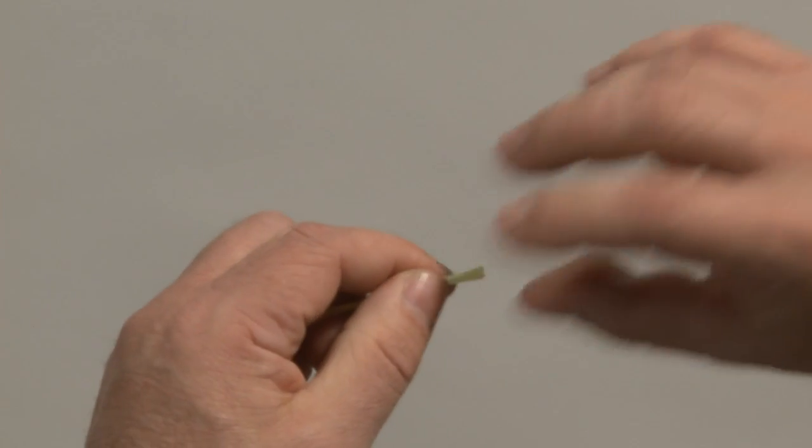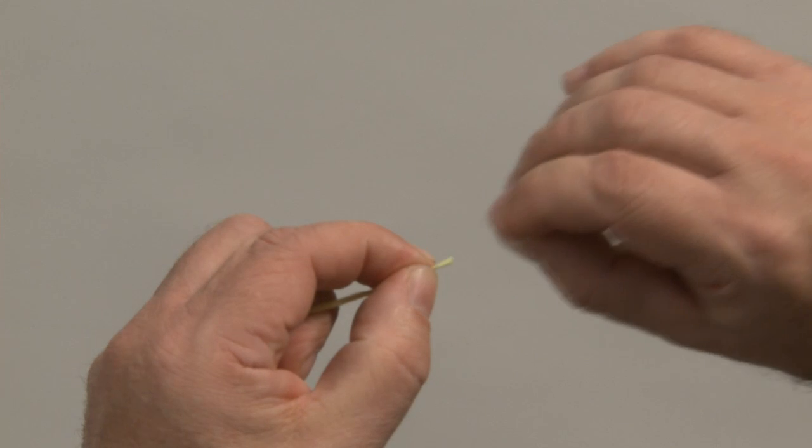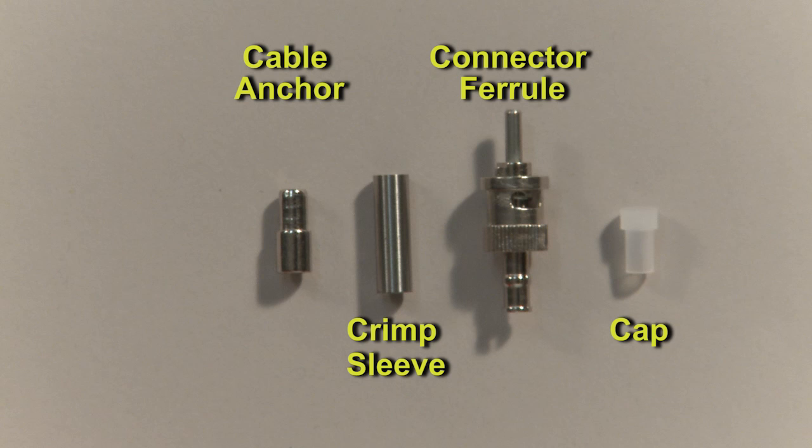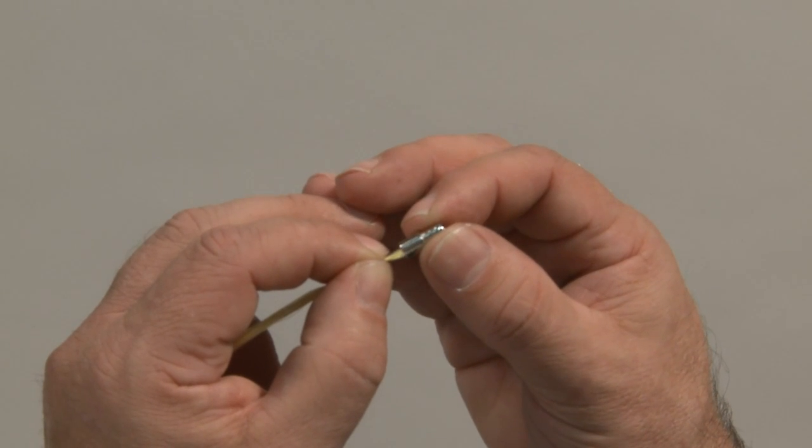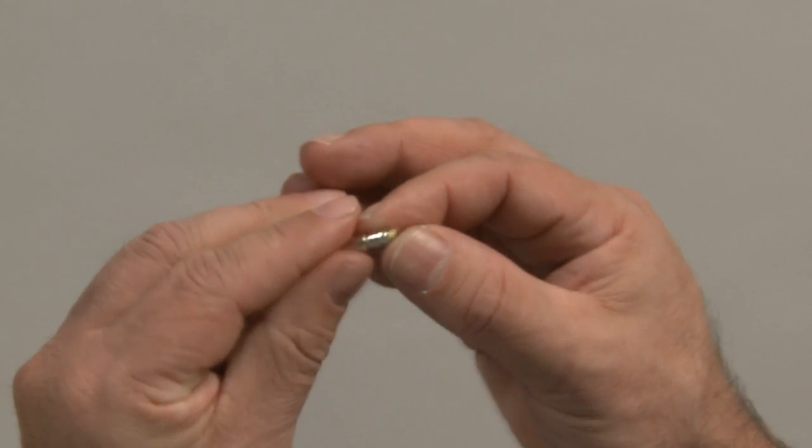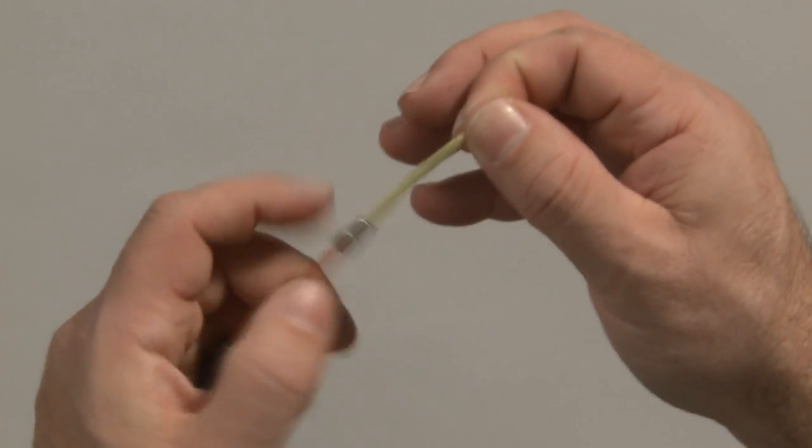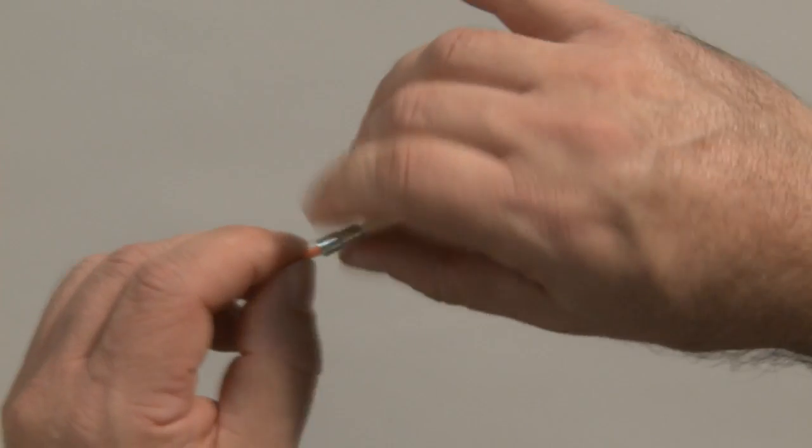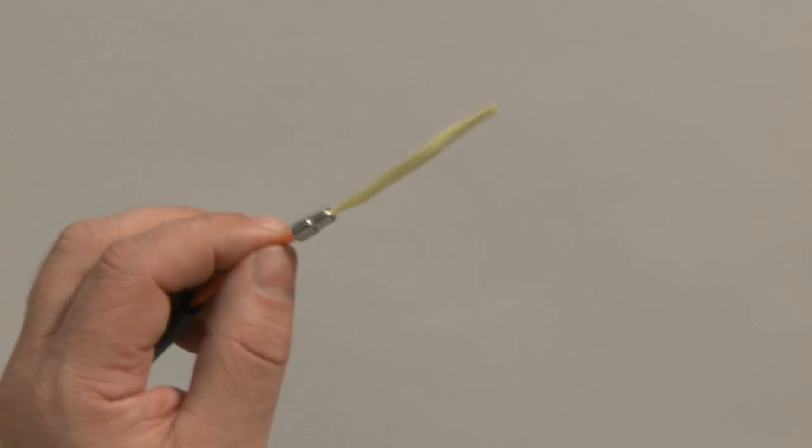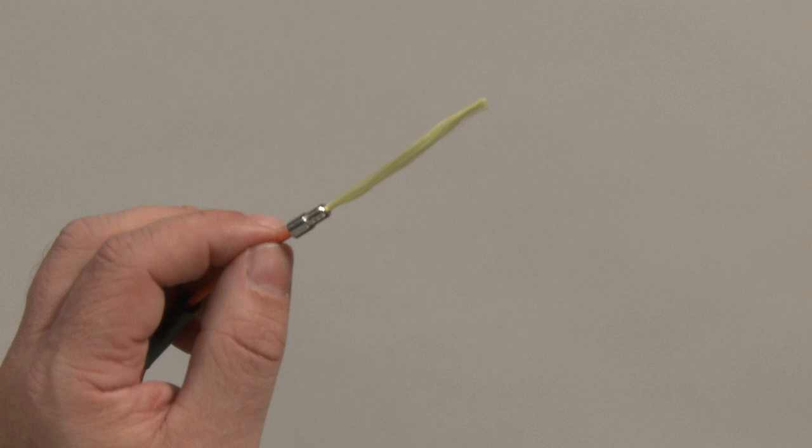Pull the aramid yarn back over the fiber. Feed the fiber and aramid yarn through the cable anchor, turning it clockwise until it bottoms out onto the cable. If a small portion of the aramid yarn does not feed through, just trim away the loose ends. This will not affect the strength or integrity of the termination.